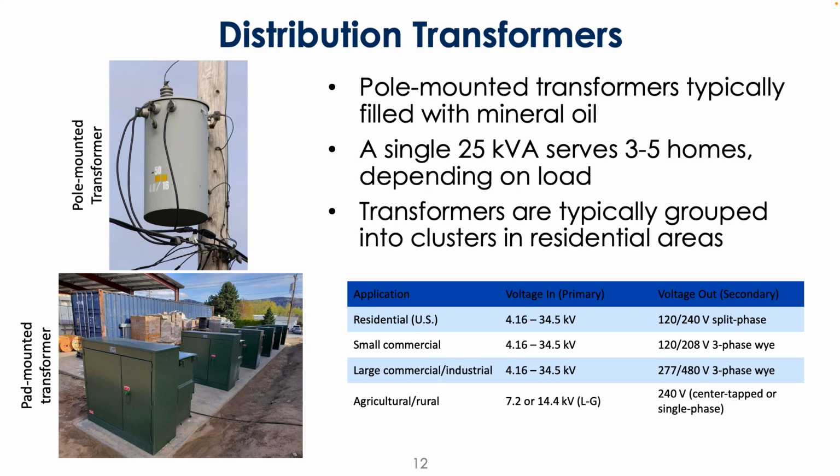Okay, and so as we talked about last week, one of the limiting factors for these transformers is its thermal rating, right? If these things get too hot, you can have damage that degrades the transformer. That could put it out of commission, or in more extreme cases render it inoperable, although there's a lot of protections against that.